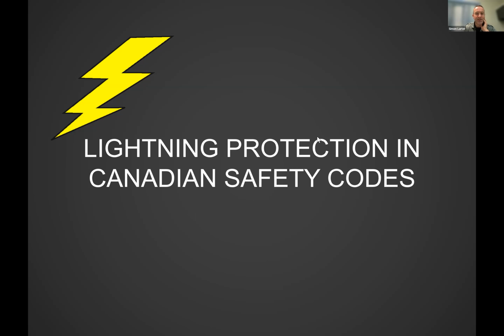Structural beams connected to lightning current mitigation system. Yes. If we use structural steel as the down conductor, then it's okay to hang other grounded systems off of it, to hang conduits, to hang sprinkler systems and all that stuff.